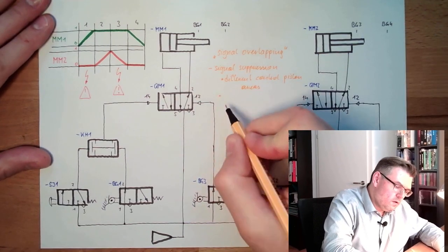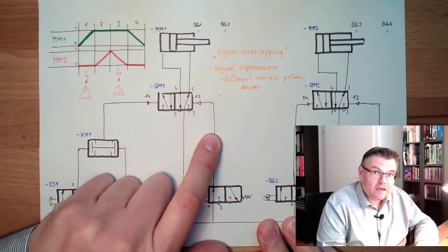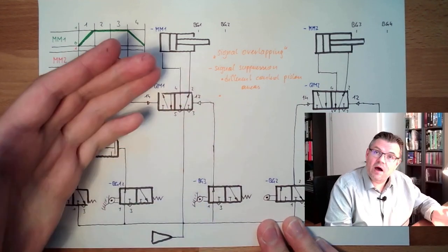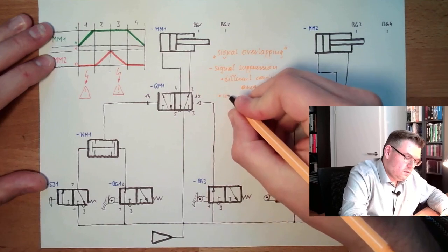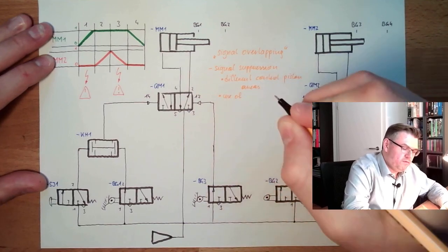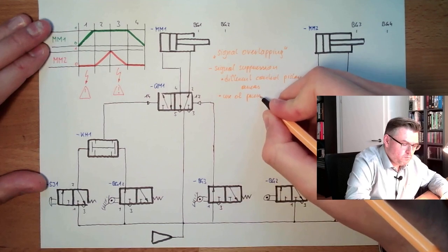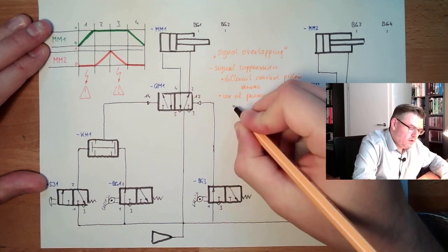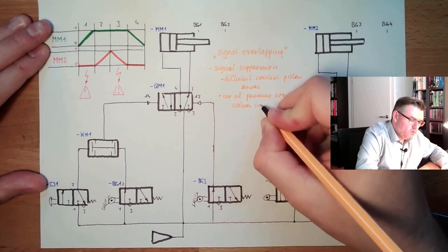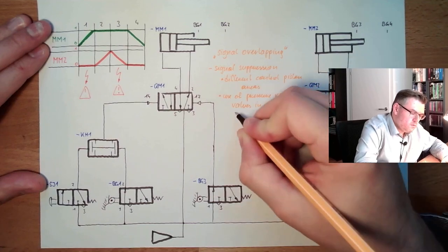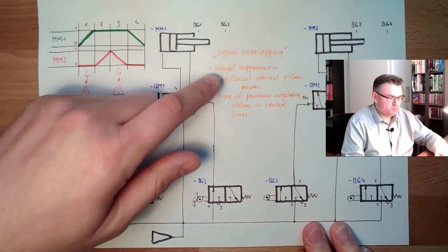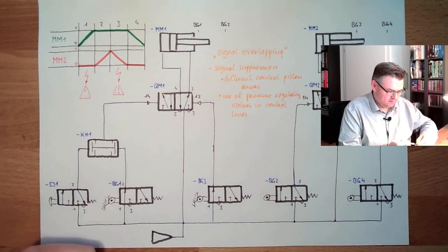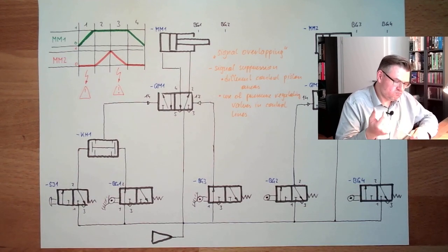Or, here in the control lines, I can use a pressure regulating valve. I simply reduce one of the pressures in the control lines, then the higher pressure is winning. Use of pressure regulating valves in control lines. This is one possibility. Signal suppression. So, to weaken one signal.